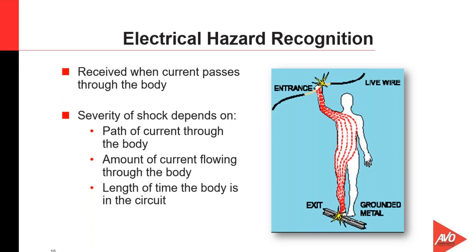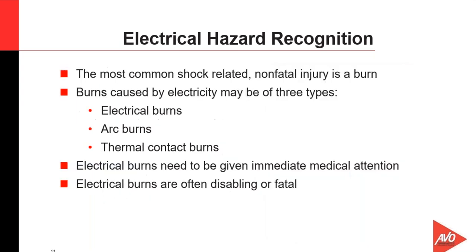The main issue with shock or current is the burning effect as the current goes through the body. This has to do with the path that the current actually takes, the amount of current flowing, and essentially how long this current is going to be flowing. Remember, the longer the current is flowing in the body, the more heating effect that you get, and you get more internal burning as the shock duration increases in time.